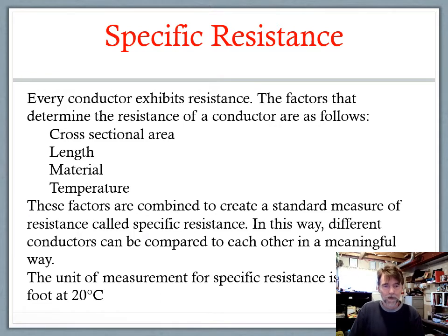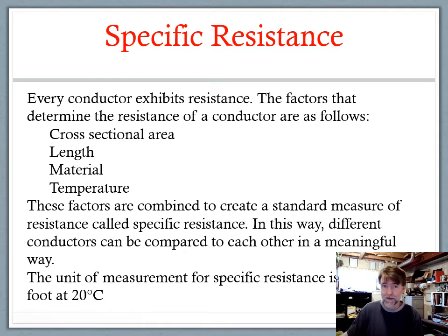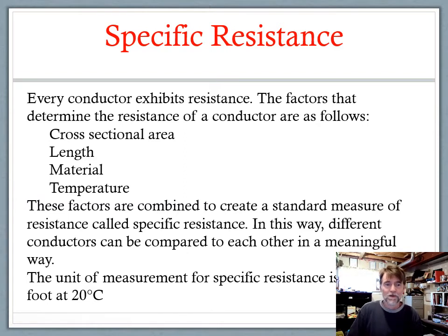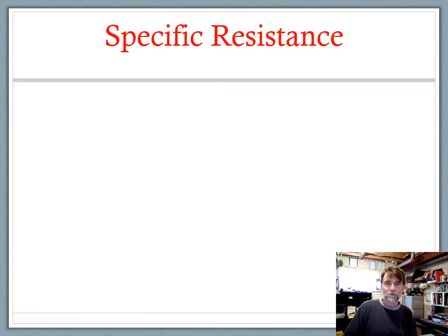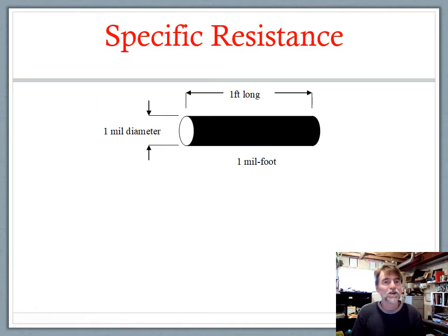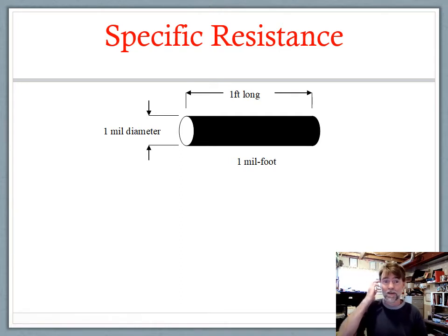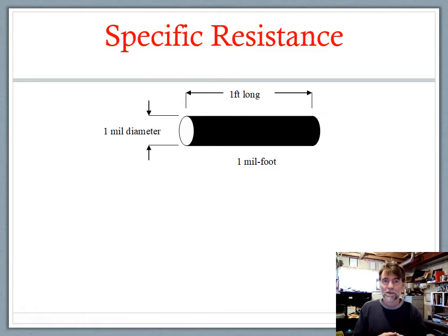The unit of measurement for specific resistance is ohms per mil foot at 20 degrees Celsius. Let's ignore the 20 degrees Celsius for now — we'll deal with temperature next. The unit is primarily ohms, because this is resistance, but ohms based on a particular condition: mil foot. That means the conductor is one mil in diameter, which incidentally means it is one circular mil, because one mil diameter squared is still one.